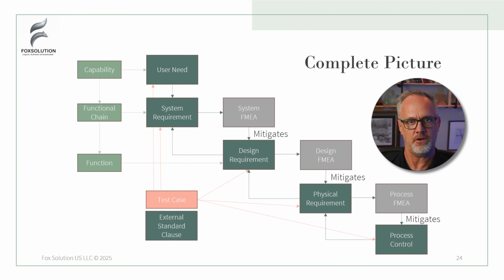So we have an industry view of everything that's needed for the different scope issues inside of development of the project, whether it's 60601 or sterilization procedures or device specific stuff, testing procedures. All of the industry understanding has been baked into the requirements model. And then finally, we have this traceability to outputs. And when we do it this way, what we end up with is a set of requirements that has all these perspectives baked into it, so that we have the best chance of getting our design requirements complete and also getting them as correct as we possibly can based on all of these different perspectives: systems modeling, risk management, external standards, the testing evidence, the whole picture.